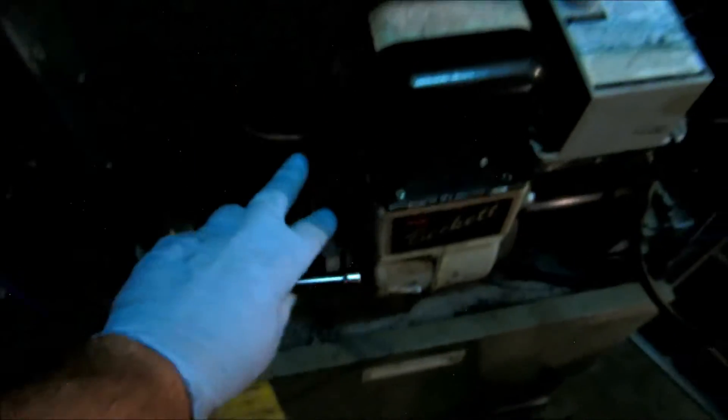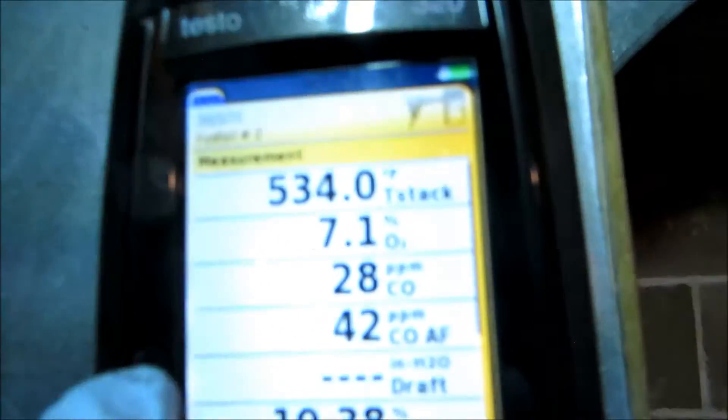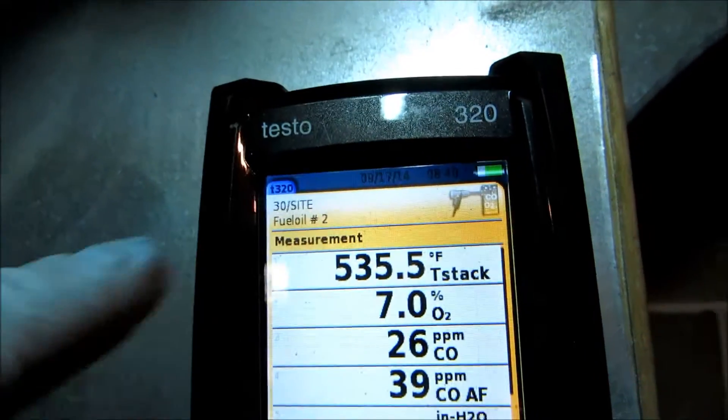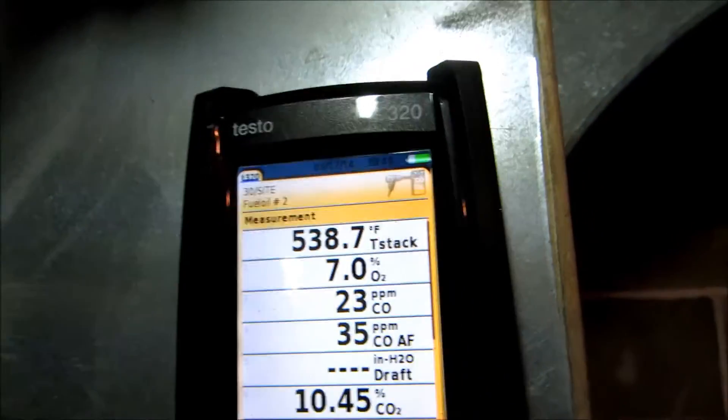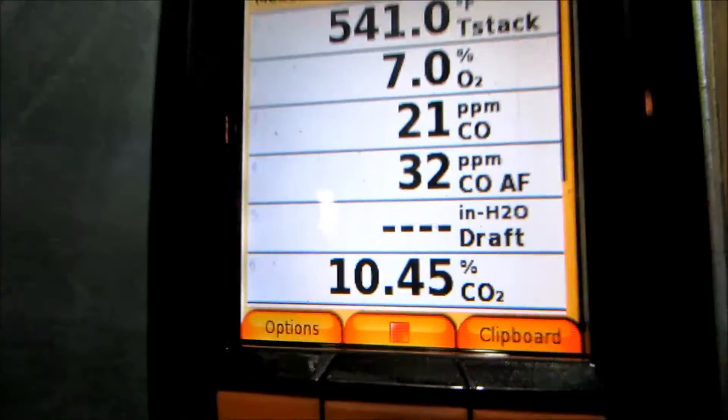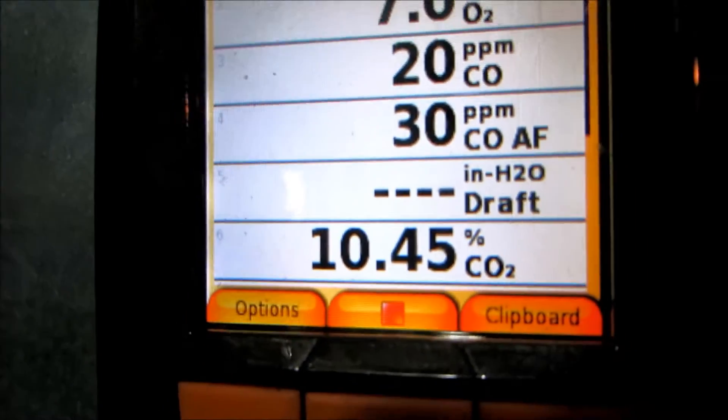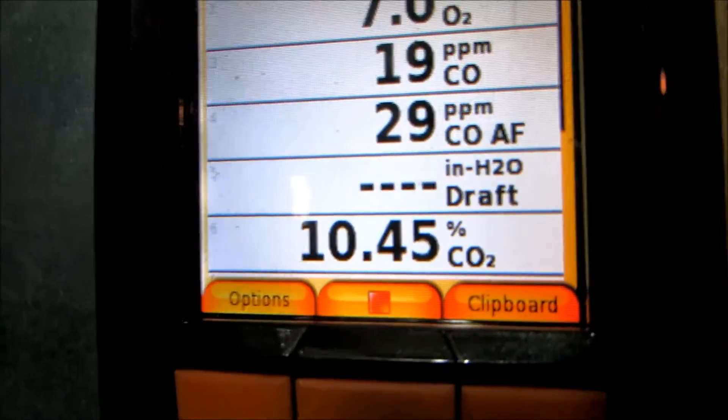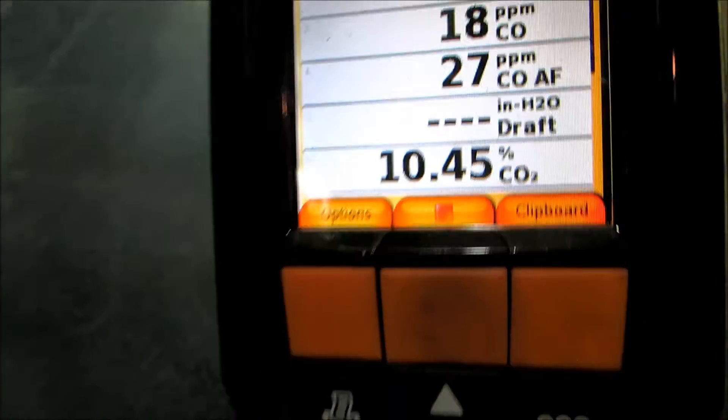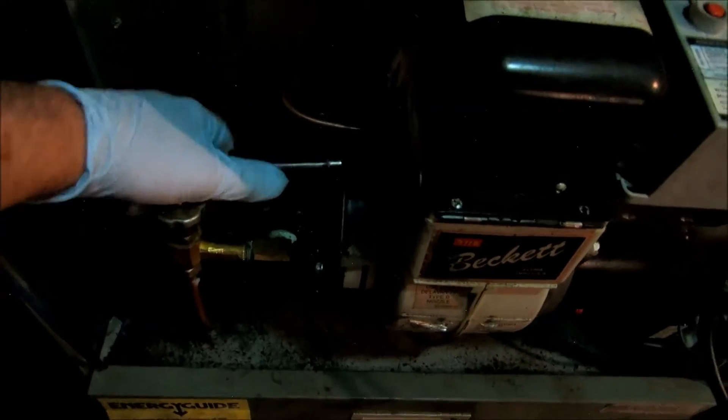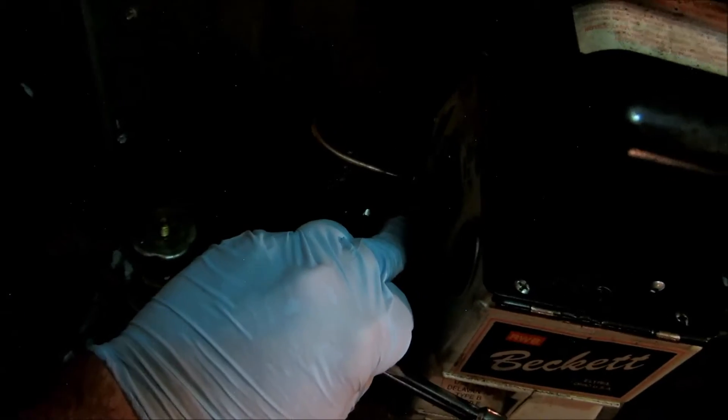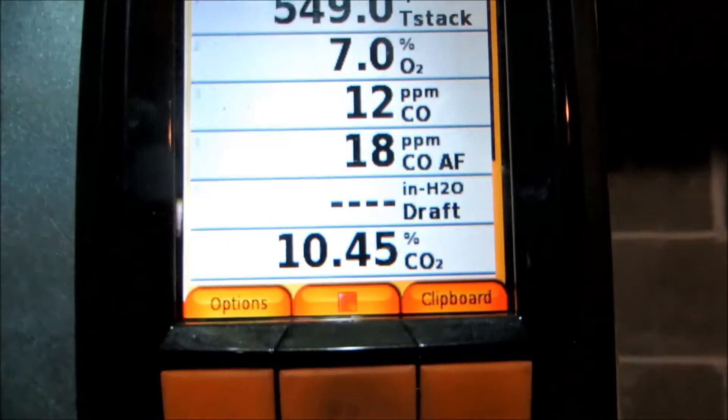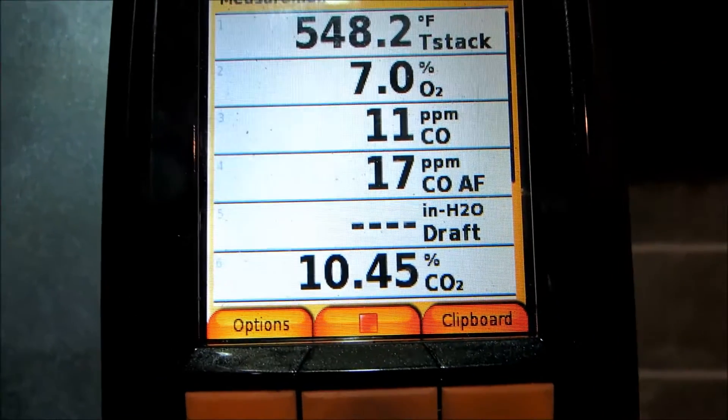Alright guys, I got myself a wrench here. I'm going to try adjusting the air band a little bit. Shut it off and started it up - a little bit of boost in the CO when you first start it, you'll get a little high dose of CO. But I want to bring that CO2 up a little bit by cutting down the air band. Let's see what happens.